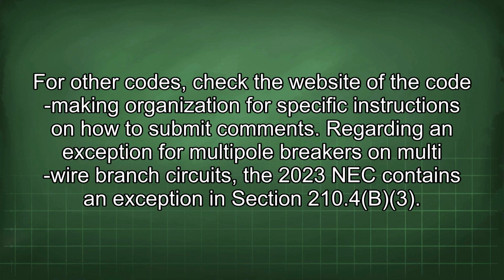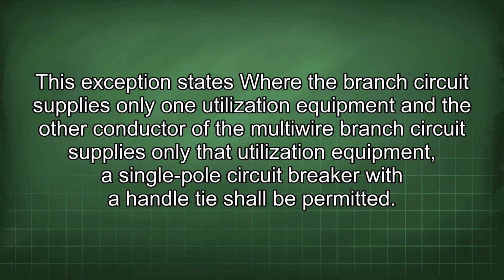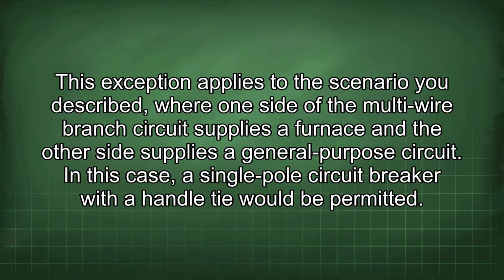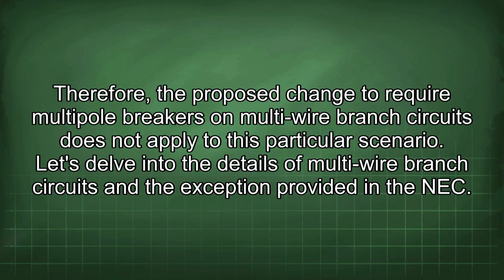Regarding an exception for multipole breakers on multi-wire branch circuits, the 2023 NEC contains an exception in section 210.4(B)(3). This exception states where the branch circuit supplies only one utilization equipment and the other conductor of the multi-wire branch circuit supplies only that utilization equipment, a single-pole circuit breaker with a handle tie shall be permitted. This exception applies to the scenario you described, where one side of the multi-wire branch circuit supplies a furnace and the other side supplies a general-purpose circuit. In this case, a single-pole circuit breaker with a handle tie would be permitted. Therefore, the proposed change to require multipole breakers on multi-wire branch circuits does not apply to this particular scenario.